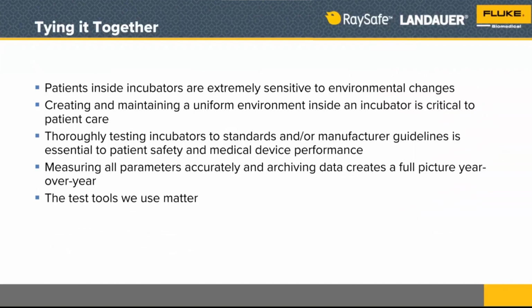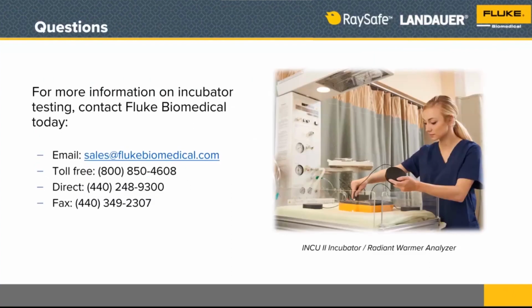Tying it all together, patients inside the incubator are extremely sensitive to environmental changes. We're creating and maintaining a uniform environment so that they can grow up. And we're going to thoroughly test infant incubators to standards or the manufacturer's guidelines in the service manual procedure. And we're going to measure all the parameters accurately and archive our data to have a good track record of the measurements that we have made, ensuring safety and effectiveness for clinical use. The test tools that we use do matter. Their traceability for their metrology and calibration matter. So you might want to take a look at our Introduction to Metrology for Medical Device Quality Assurance webinar for a little bit more information on that. All right.